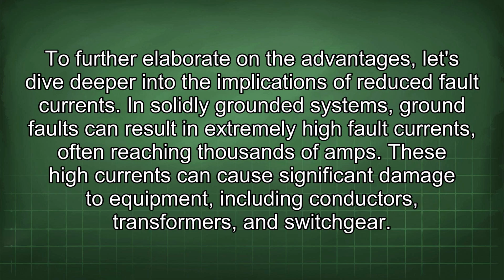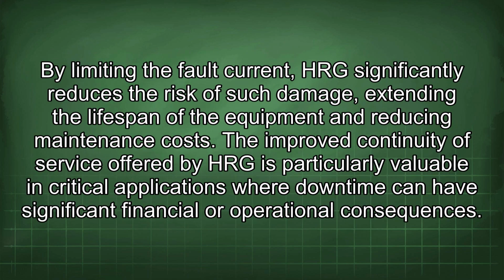To further elaborate on the advantages, let's dive deeper into the implications of reduced fault currents. In solidly grounded systems, ground faults can result in extremely high fault currents, often reaching thousands of amps. These high currents can cause significant damage to equipment, including conductors, transformers, and switchgear. By limiting the fault current, HRG significantly reduces the risk of such damage, extending the lifespan of the equipment and reducing maintenance costs.